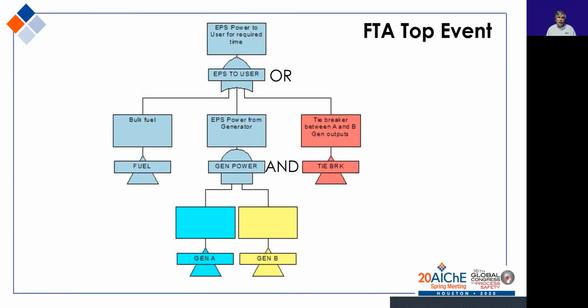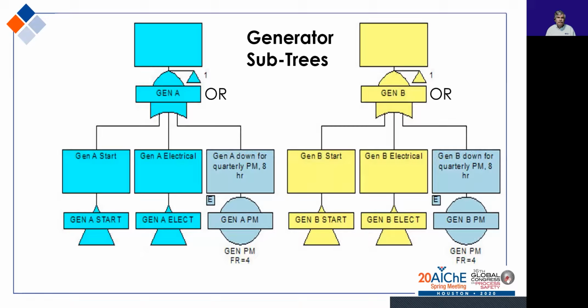If any of the problems from the three input gates below it occur, there is no power to the EPS for the required time. The generator power gate is an AND gate because if either generator runs, we should have enough power for the load. If the full load needs to go to one generator, then the tiebreaker is needed.